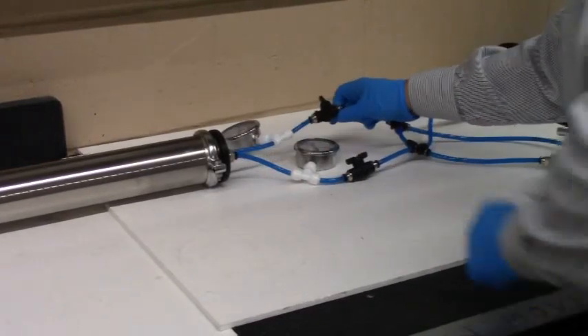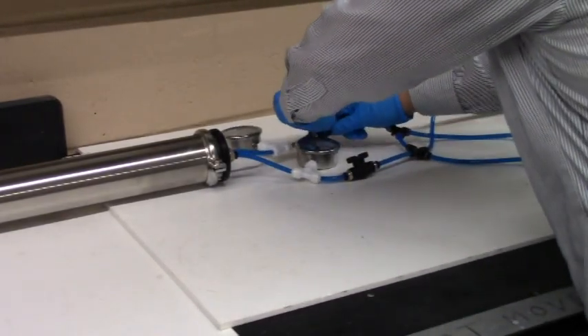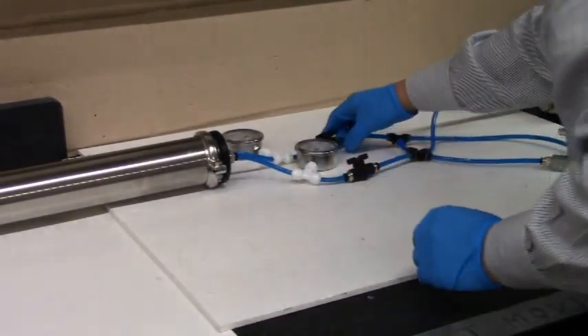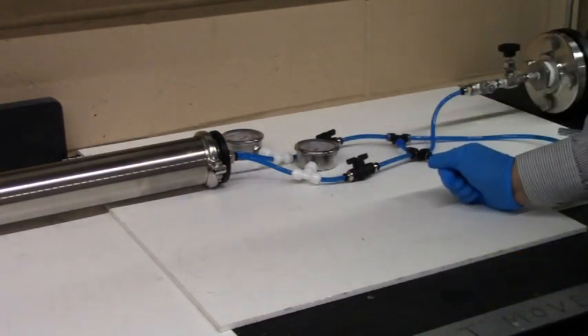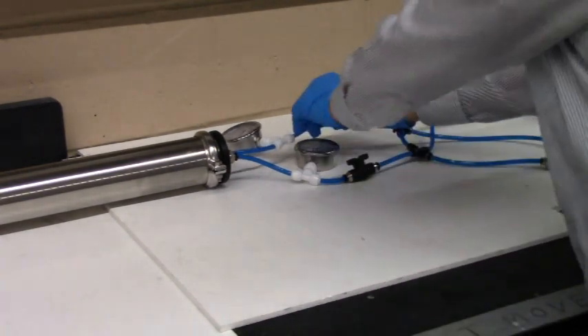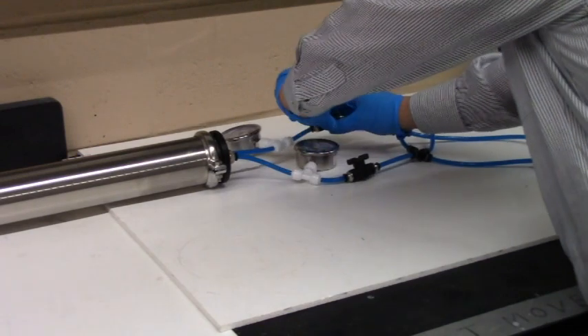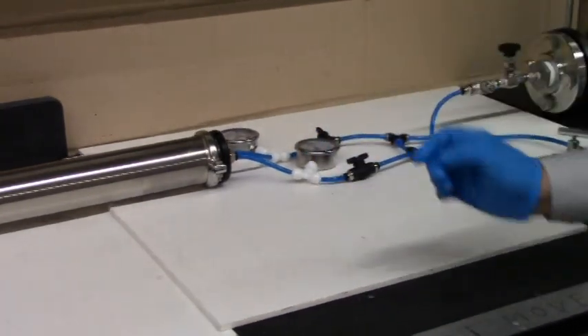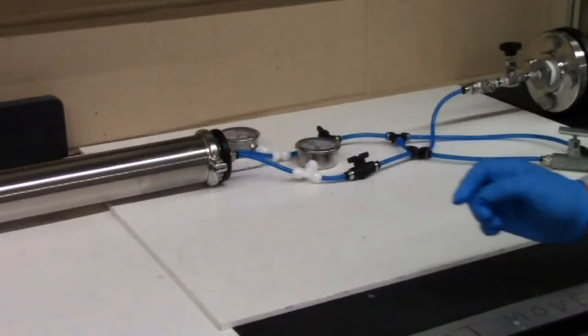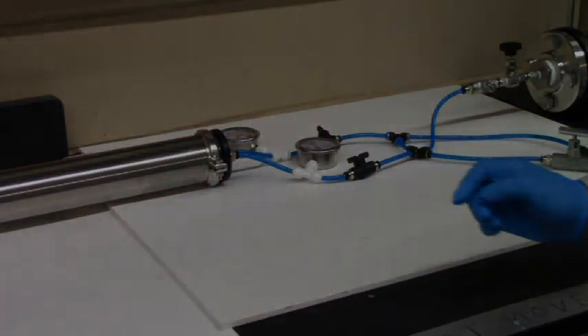Open the backwash inlet valve to flush both sides of the membrane filter to remove air bubbles and dirty things, if any. Close the backwash valve after a while. This step usually increases the filter inlet pressure.